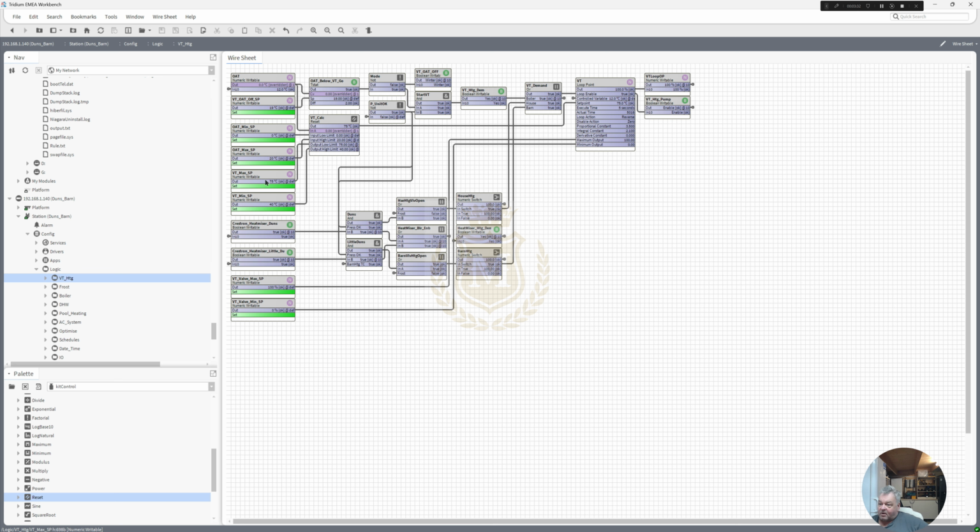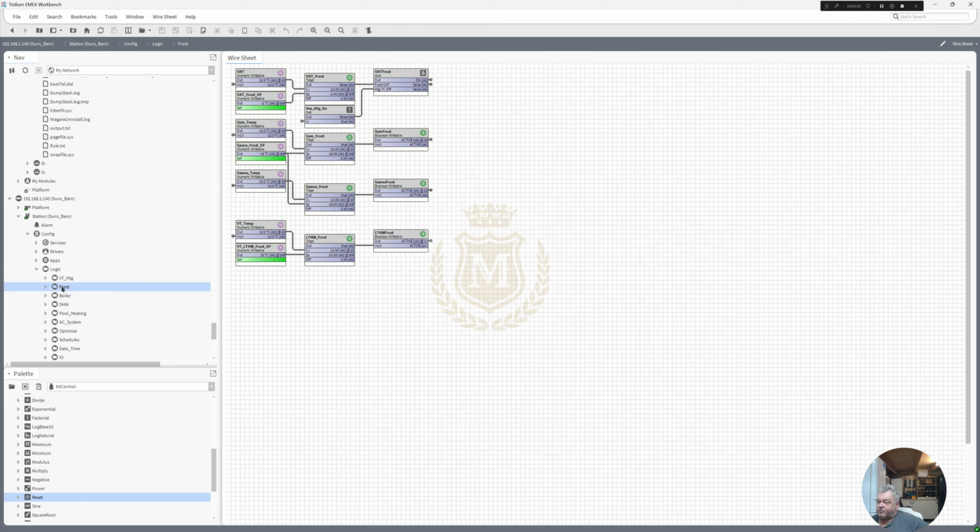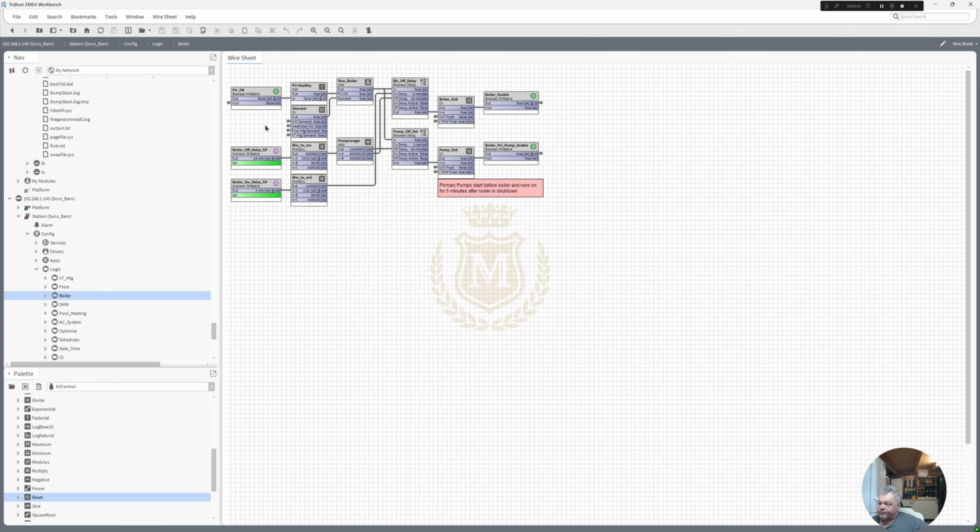Anyway, just quickly go through the logic. So frost logic, it's just your normal temperature, your set point going into a T-stat with a differential of 2, which is 1 degree either side. And the boiler logic, very simple, pressurization unit. There's no fire alarm here. Any demands from hot water, heat miser, pool or VT heating. So long as the PU is okay, pressurization unit, we can then start.